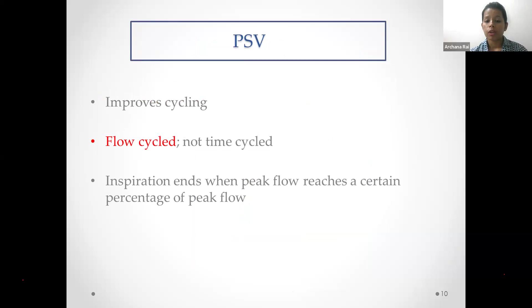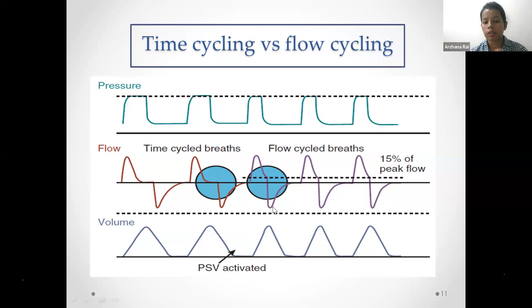The first half on the left side is time cycled breaths. In this, we can see that because of the time cycling, there is an inspiratory hold. And when this mode is changed to pressure support ventilation, it changes into flow cycling. Once the flow reaches 15% of the peak flow, the inspiration ends and it goes into the expiratory phase.